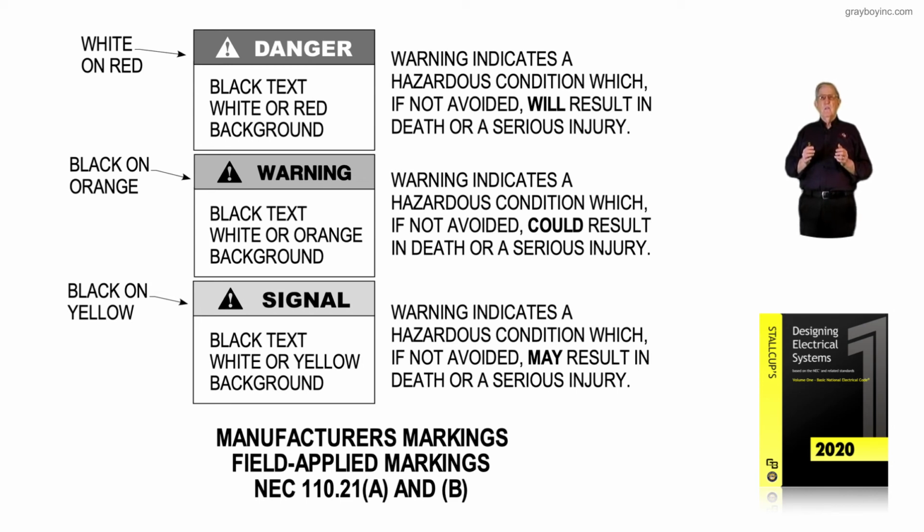So we can well see then that 110.16(A) and (B), as well as 70E 130.5(H), along with 110.24(A), has been satisfied with field markings by the contractor, as well as by the owner of the equipment. So this illustration does comply with field marking in accordance with NEC 110.24(A) as well as (B).